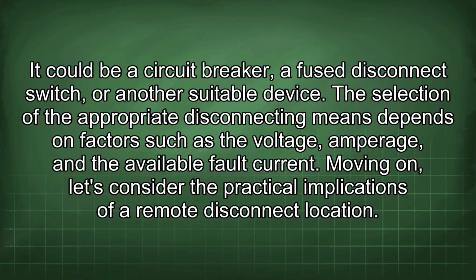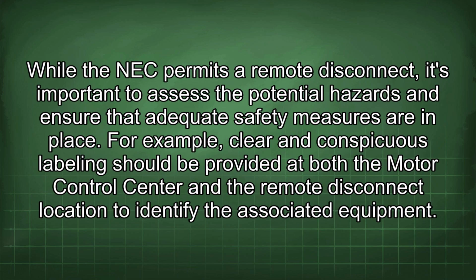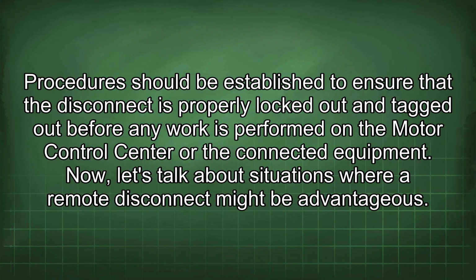Moving on, let's consider the practical implications of a remote disconnect location. While the NEC permits a remote disconnect, it's important to assess the potential hazards and ensure that adequate safety measures are in place. For example, clear and conspicuous labeling should be provided at both the motor control center and the remote disconnect location to identify the associated equipment. Procedures should be established to ensure that the disconnect is properly locked out and tagged out before any work is performed in the motor control center or the connected equipment.